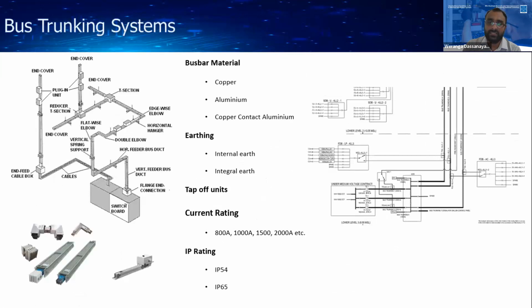As I mentioned earlier, there is another system called the bus duct system. Instead of cables, we can use this kind of system. There you have to see the bus bar material. That means in this system, you can use copper as the conductor, or we can use aluminium as the conductor. Or there is another called copper contact aluminium. That means inside this bus duct system, the conductors are made of aluminium, but at the end, this aluminium conductor is converted to a copper contact using a bimetallic reaction. There is a technique to convert this aluminium conductor into copper conductor at the edges of the bus duct system.